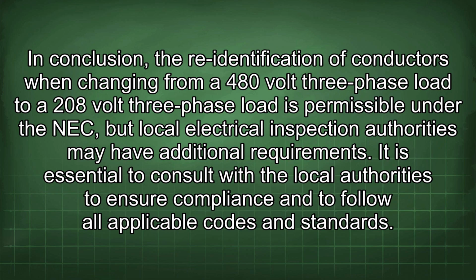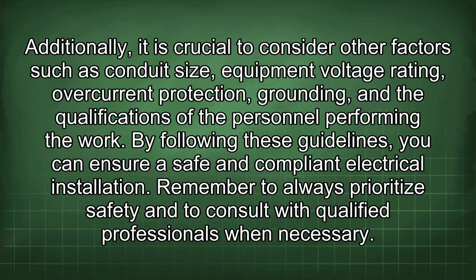In conclusion, the re-identification of conductors when changing from a 480-volt three-phase load to a 208-volt three-phase load is permissible under the NEC, but local electrical inspection authorities may have additional requirements. It is essential to consult with the local authorities to ensure compliance and to follow all applicable codes and standards. Additionally, it is crucial to consider other factors such as conduit size, equipment voltage rating, overcurrent protection, grounding, and the qualifications of the personnel performing the work. By following these guidelines, you can ensure a safe and compliant electrical installation. Remember to always prioritize safety and to consult with qualified professionals when necessary.